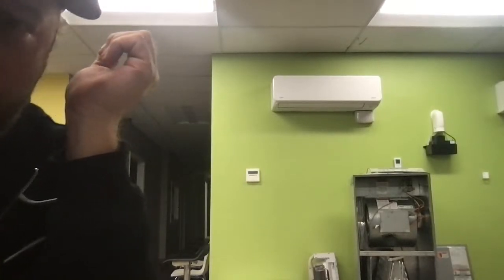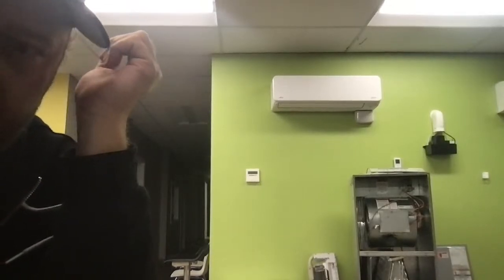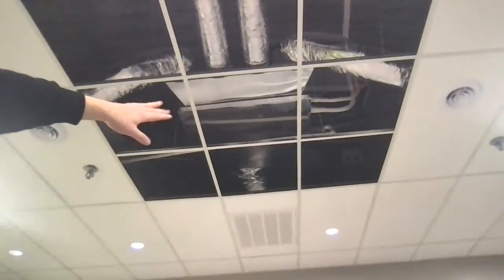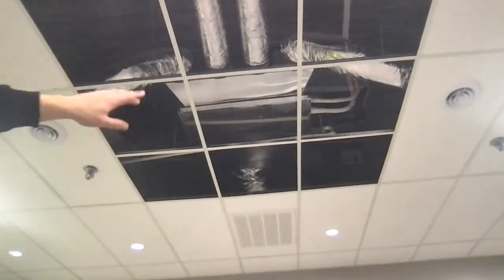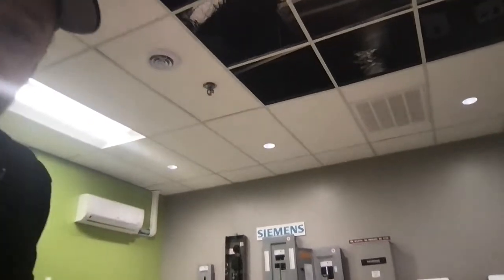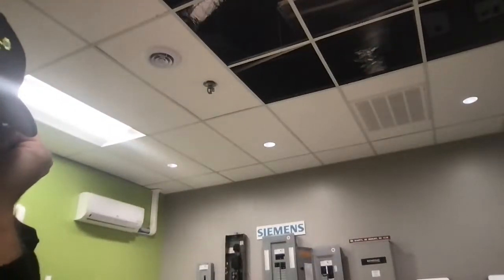You can put the attic style unit in a basement ceiling, as long as it's open, since you can't really conceal this to a degree. You need at least a foot of clearance between anything we install and what's below. You have to think about beams and which way the joists go, because then you might be dealing with bulkheads and things like that. That big duct at the back is even bigger, so if it's going into a mechanical room or similar space, maybe you can conceal it somewhat, but it really just depends.